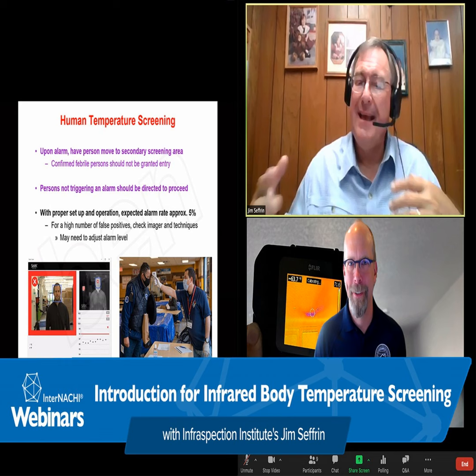Also, be certain to choose a sturdy unit with a fluid function head. Make certain that the selected lens is matched to the imager chassis for imager temperature measurement accuracy. And determine, if possible, if the imager can be remotely operated. If not, choose a comfortable position for the operator to watch the imager and be certain to allow for adequate social distancing. A myth I would like to dispel at this point is that this is not a technique where we set up an imager and walk away. You have to have an operator watching this.